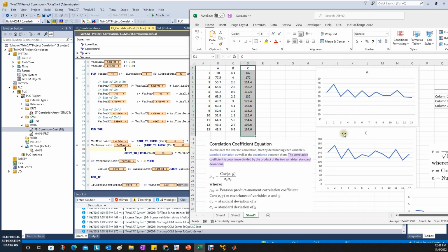For example, in the normal run, the temperature and the pressure coefficient should be within a certain range, for example around 0.8 to 0.9. But if the temperature is doing something wrong, for example going high in a short moment, then definitely this coefficient result will decrease dramatically. Then we can use this coefficient value to do some diagnostics. This basically makes your system very smart, it can predict something, or learn the relationship between different variables.